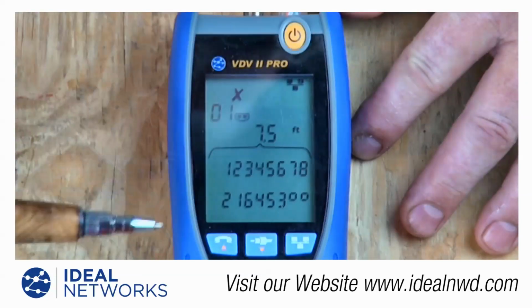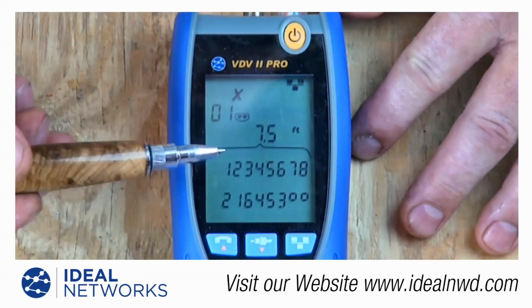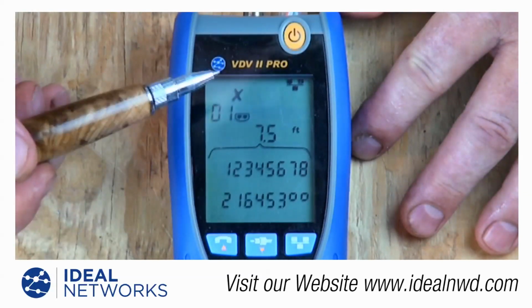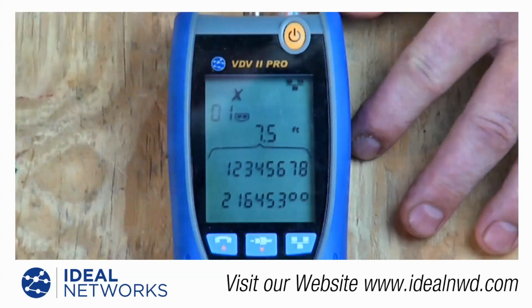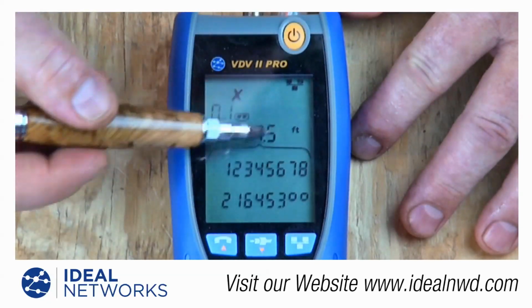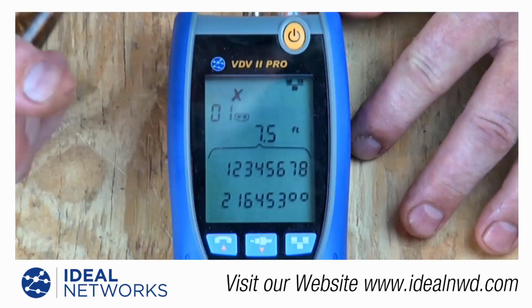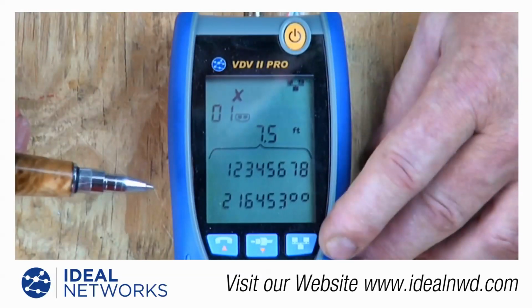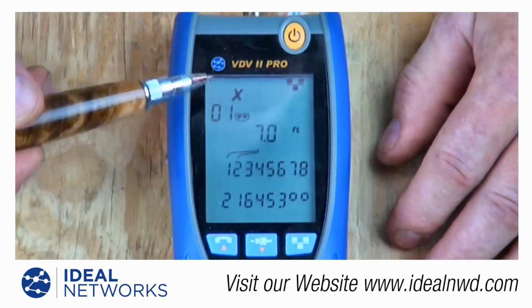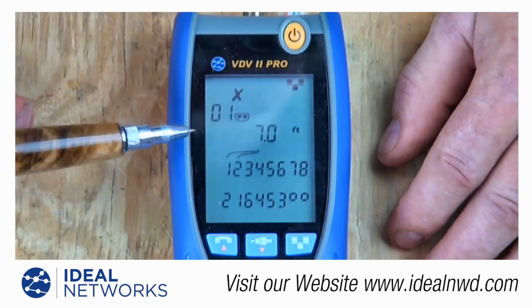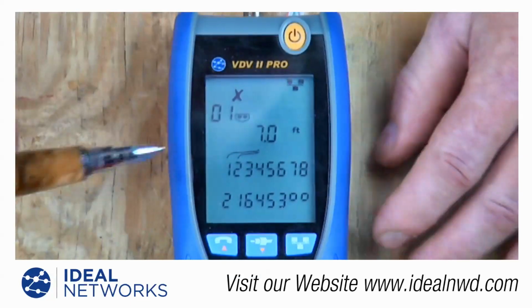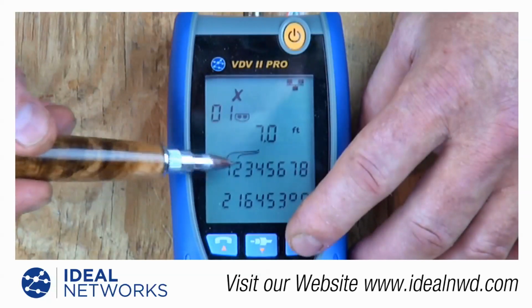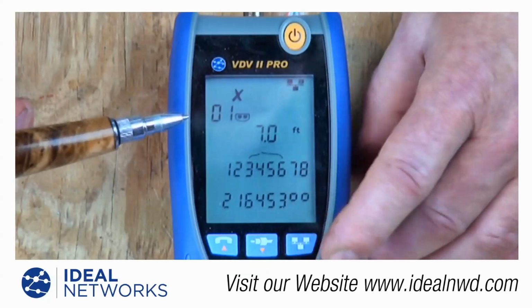One nice feature of the TDR function is we can get an idea of where that open might be in the cable, either closer to me or farther out. We know the overall cable length is around 7.5 feet, but by pushing the data button, I can look at the different length of each individual pair. This is saying pair 1 and 2, this pair here, is around 7 foot long.